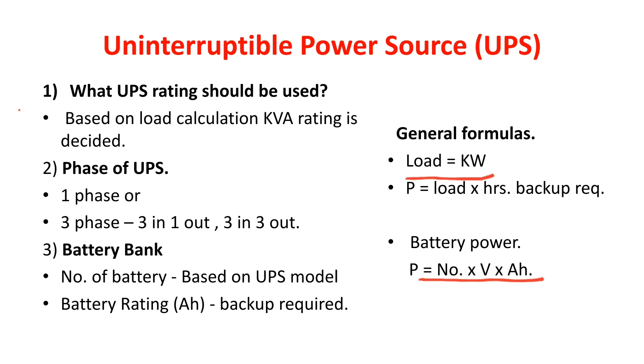Now on the right side there are some general formulas which are used to calculate all this. We calculated the total load which is to be connected to the UPS. Multiplying this load by the hours of backup required, we get some value. Equating this value with the battery power, like the number of batteries multiplied by the voltage of the batteries and the AH of the batteries, from here the battery AH rating is calculated. But remember, this is a general formula. Some other factors are also considered while calculating battery AH.